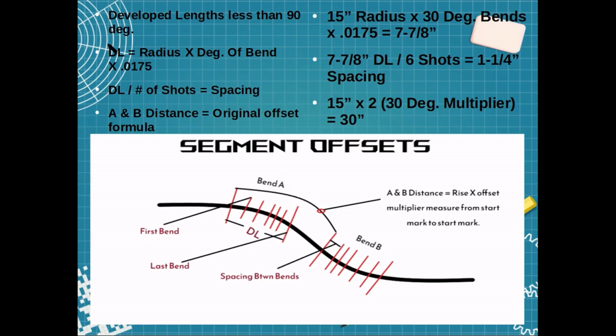Here's the formula: DL means developed length. The developed length equals the radius times the degree of bend times 0.0175. First, figure out what the radius is for your two bends — Bend A and Bend B. Once you have that information, fill in the formula and it'll give you the developed length.